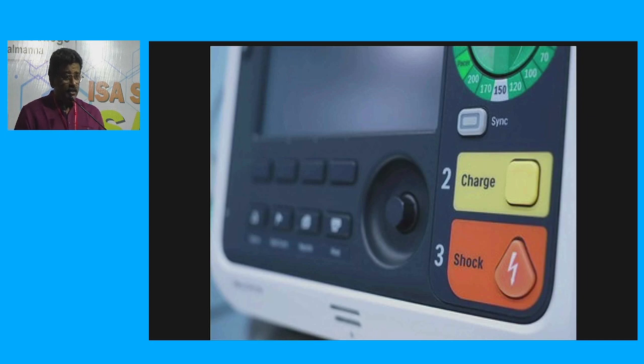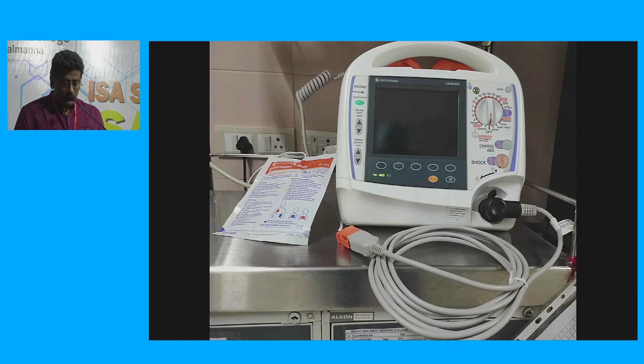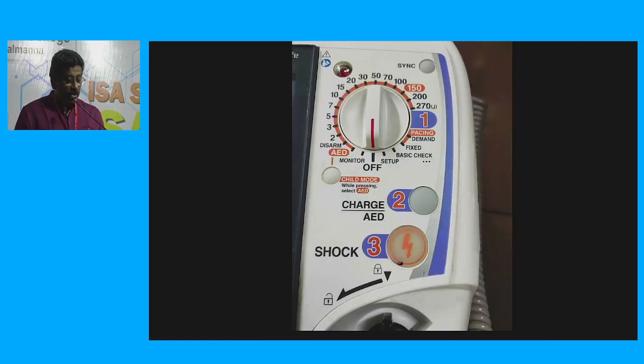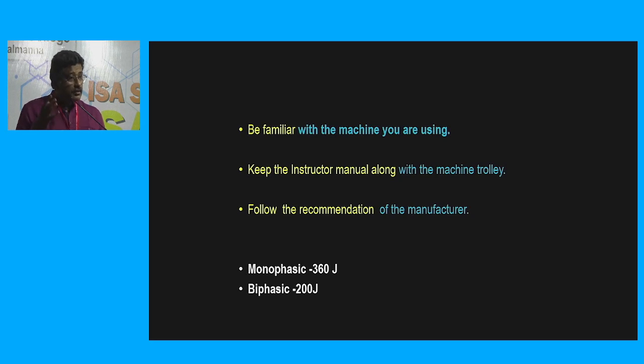But I was really surprised to see that the hospital where I am working now has a biphasic defibrillator with 270. So you cannot completely rely on these numbers. You should always try to keep the manual handy. You should be familiar with your machine beforehand, then only you can use it.